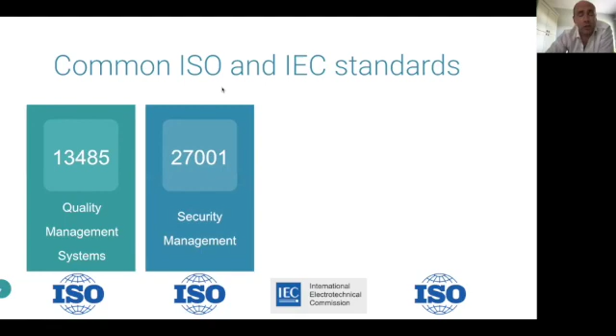Obviously, cybersecurity is a huge issue with AI. So you will also likely need to get audited for 27001, the security management standard. If you're building software, you will need to adhere to IEC 62304, which is the software lifecycle development process. And this is what the FDA are basing their proposals on good machine learning practice. They're taking into account lots of the detail of 62304.